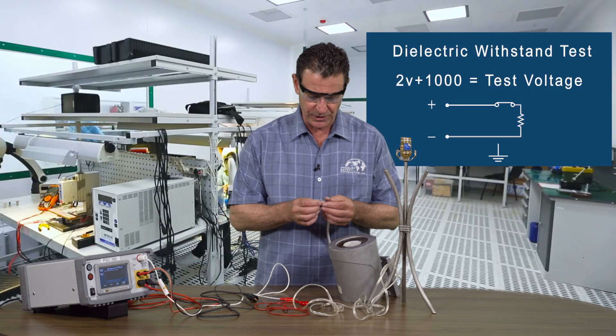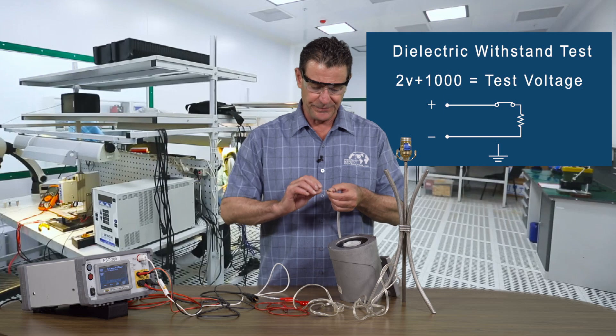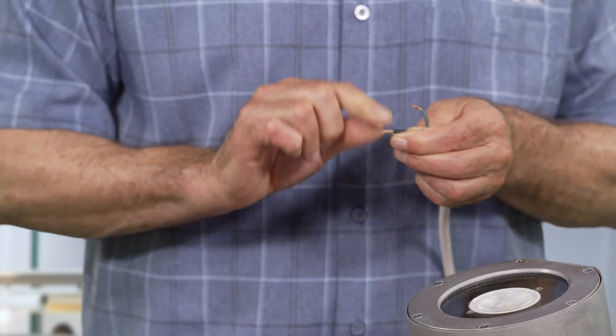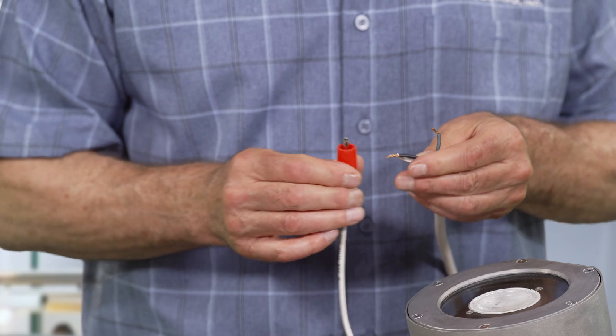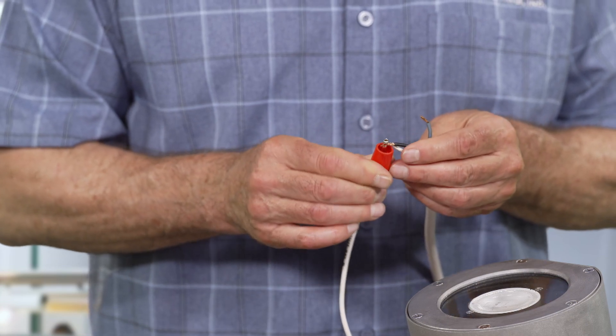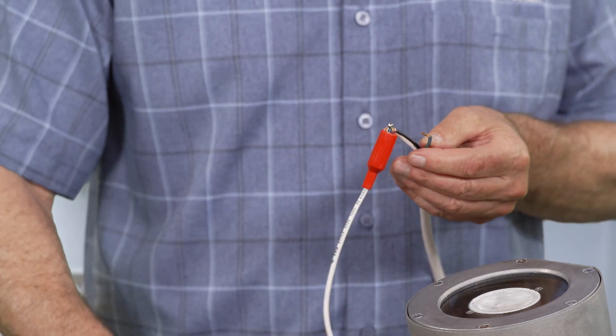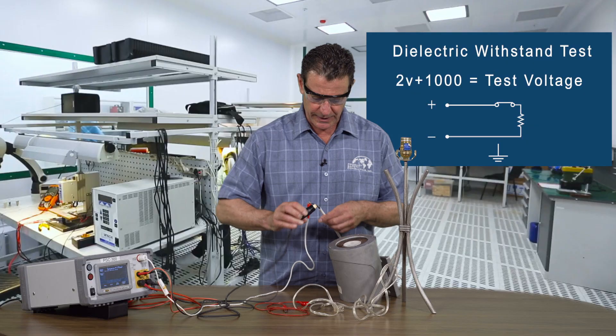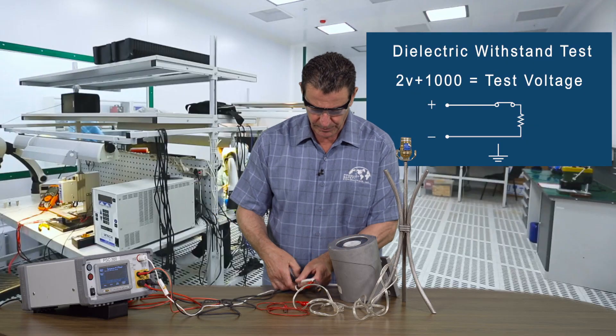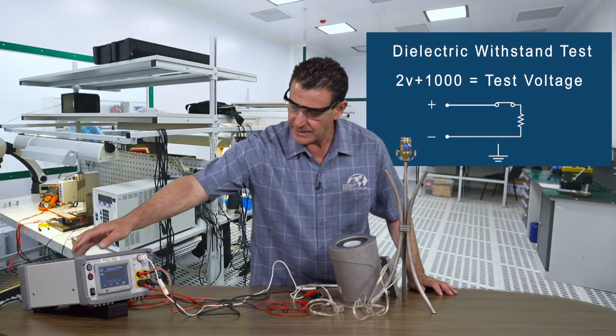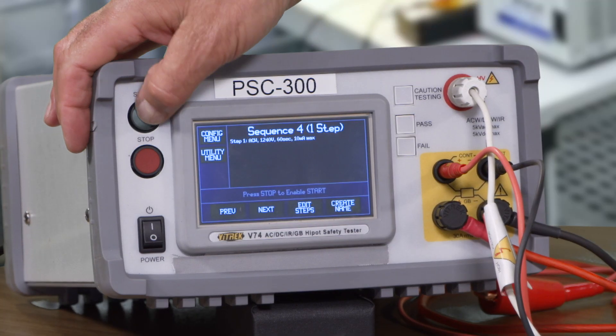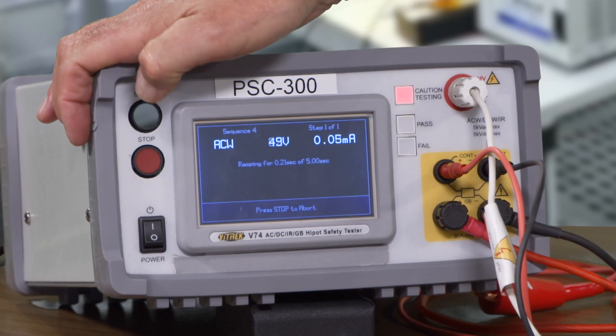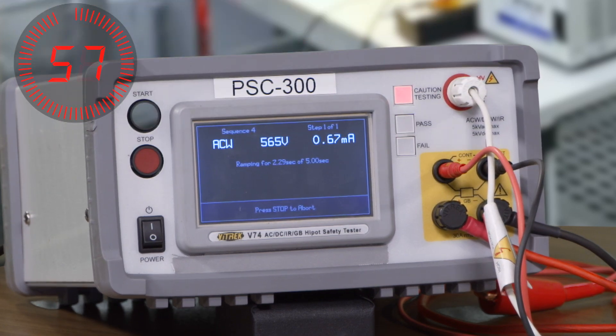So the insulation system test dielectric test as indicated we're going to tie line and neutral together. We're going to put the hot lead of the machine on that node and then we're going to take the return lead and put it on ground and I am not going to hold this. Remember it's 1200 volts. The test is actually 60 seconds and off it go.